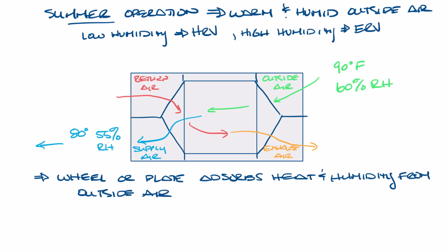From here, it moves into the HVAC system, and maybe there are cooling coils to get it to 55 degrees and 50% humidity to supply the space. The ERV or HRV reduced the energy needed to cool the air down by taking some of the heat and moisture out of it before it entered the cooling coil.